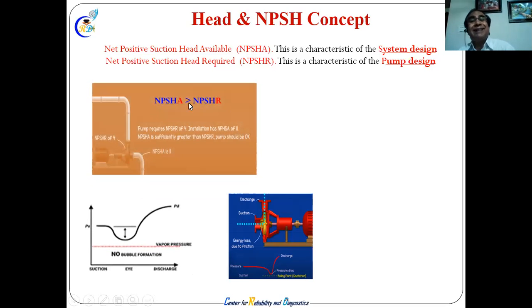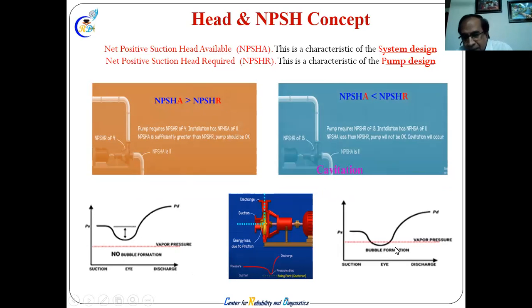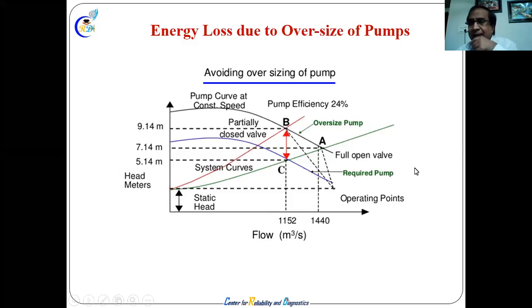So availability should be greater than the requirement to avoid cavitation, right? To avoid cavitation, this is the cavitation line. So to avoid cavitation it should be above, and whenever it is less than that, it will go down, cavitation bubble formation will occur. And what is the effect? It will affect the entire efficiency, and it affects energy also. Total energy will also be more. You are pumping less water, but the pump is running, and it is like a heater working. So avoid oversizing of pumps, which we have already discussed in the 500 cubic meter and 300 cubic meter previous examples.